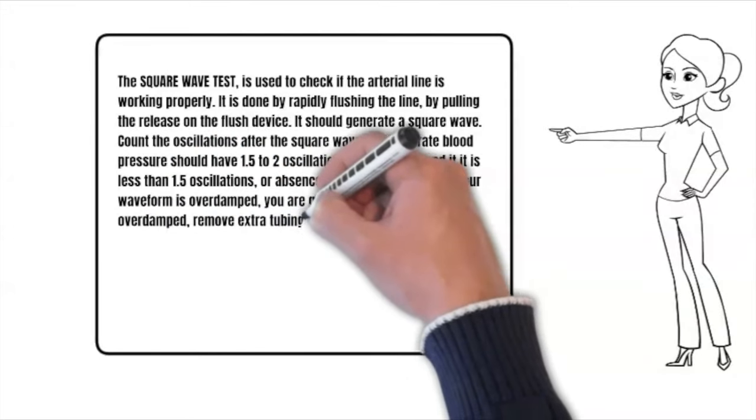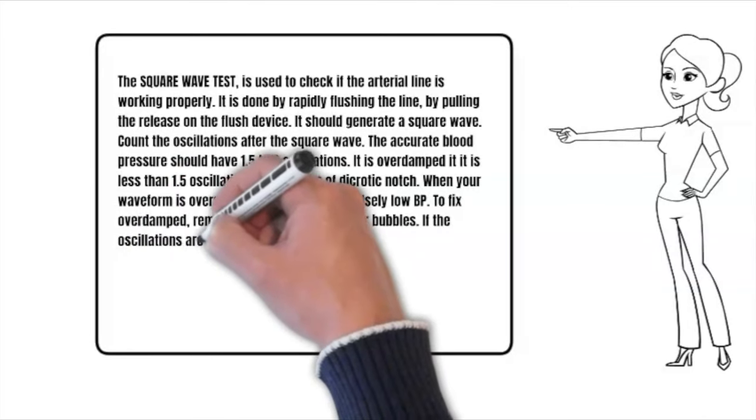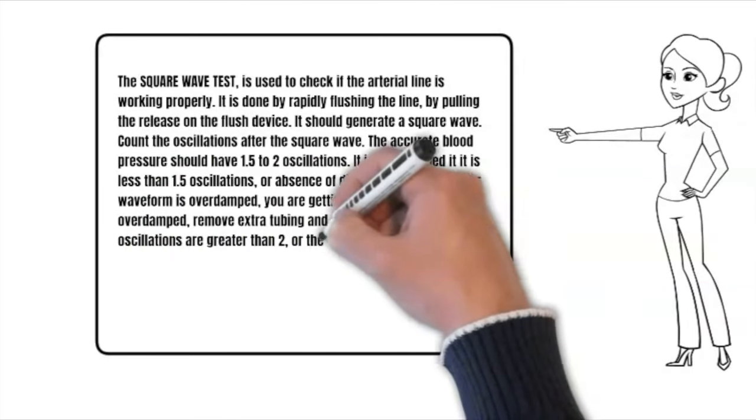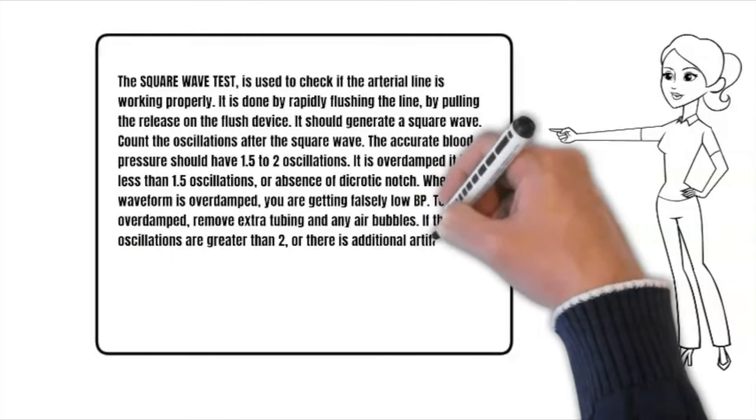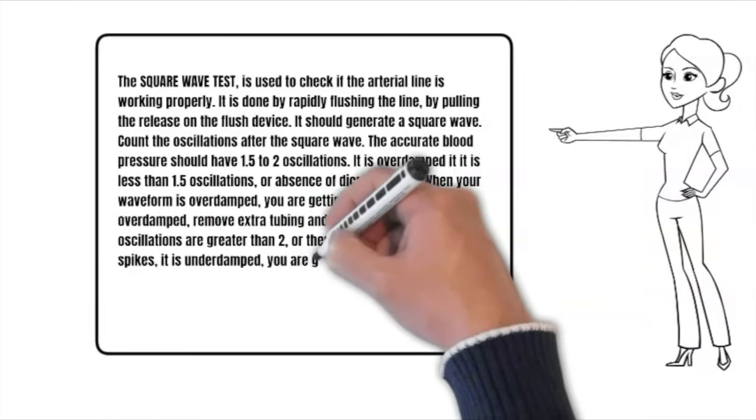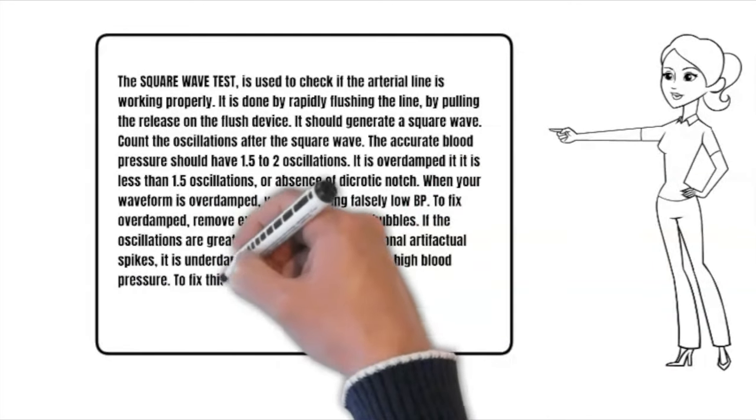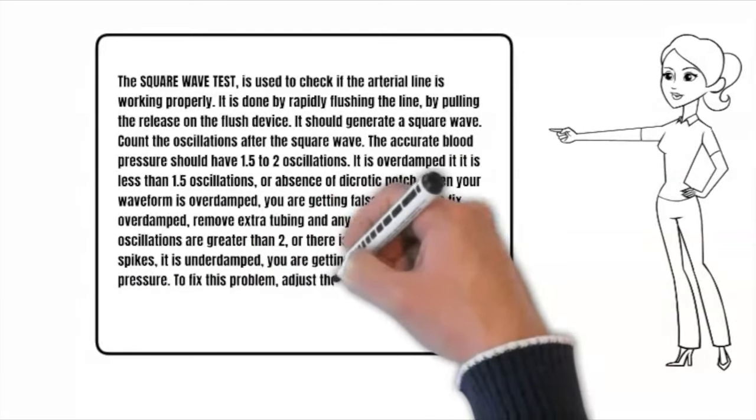Check the oscillations. If the oscillations are greater than 2 or there are additional artifactual spikes, it is underdamped. You are getting falsely high blood pressure. To fix this problem, adjust the filter settings of the monitor.